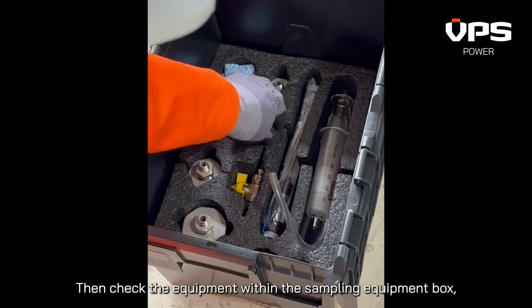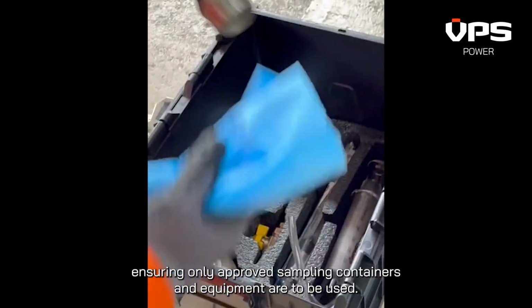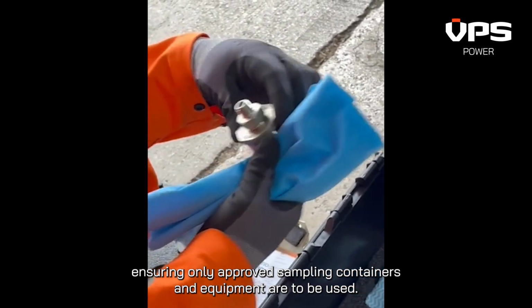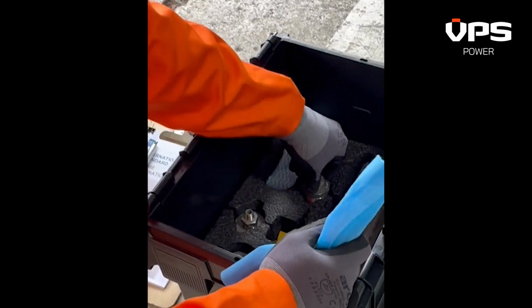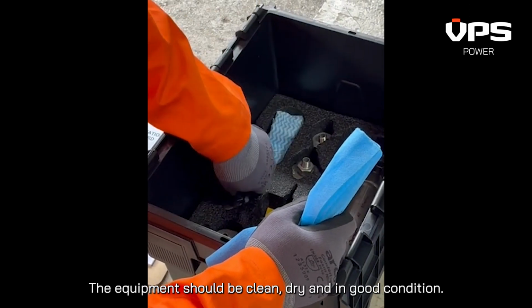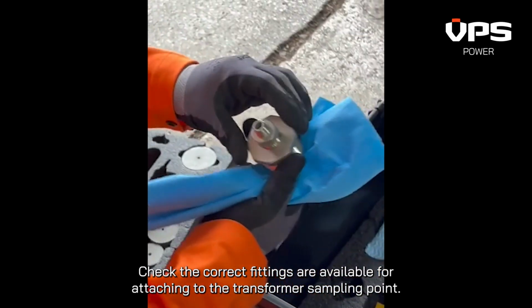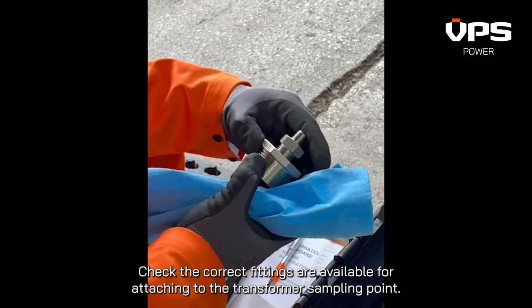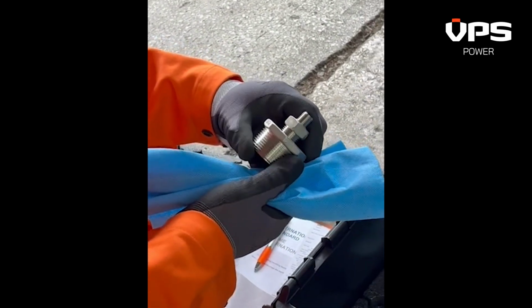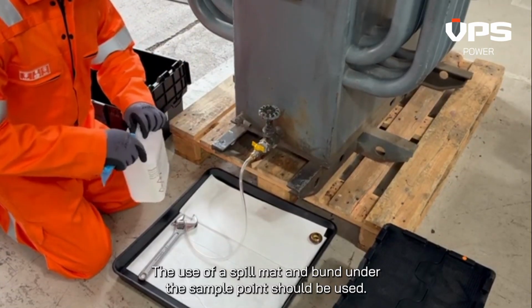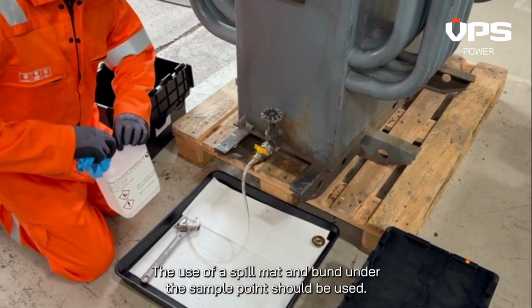Then check the equipment within the sampling equipment box, ensuring only approved sampling containers and equipment are to be used. The equipment should be clean, dry and in good condition. Check the correct fittings are available for attaching to the transformer sampling point. The use of a spill mat and bund under the sample point should be used.